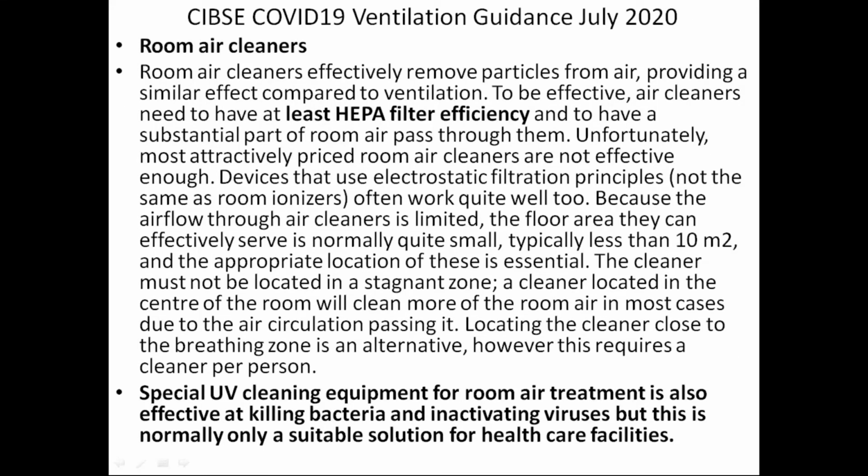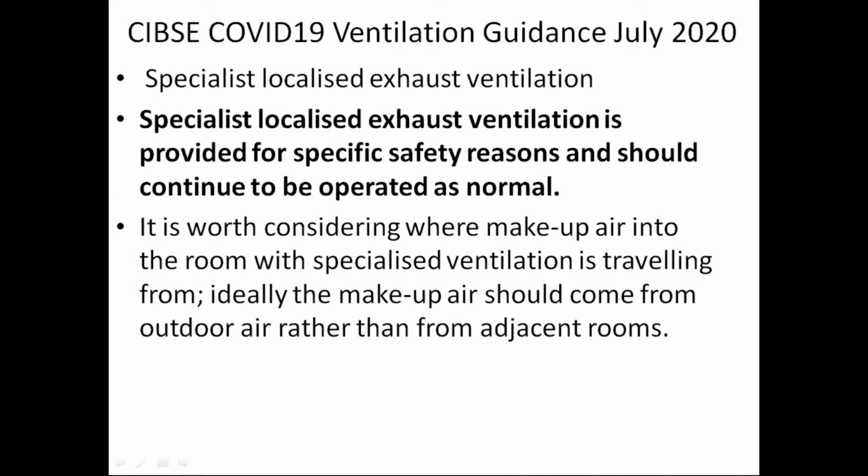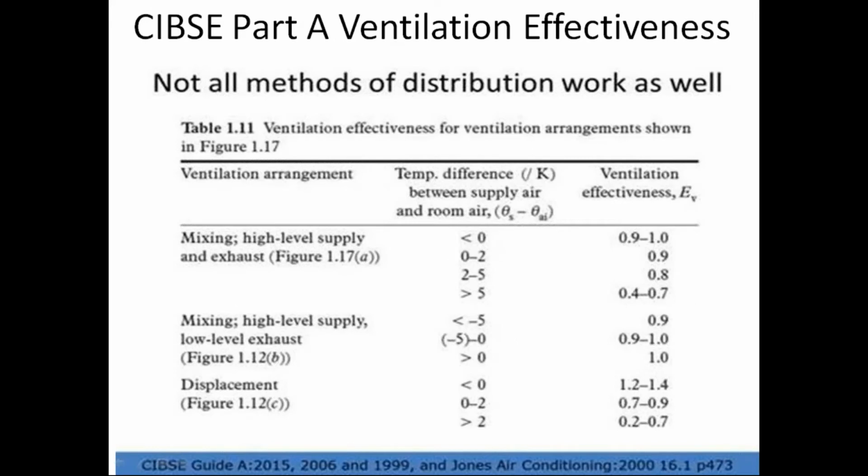Room air cleaners are acknowledged within CIBSE, but they have to be HEPAs, and they have to be to the standard that Camfil explained on previous ASHRAE presentations. They do acknowledge UVC as well. Local exhaust is important, particularly where you have AGPs, and catching the source locally and dumping it in a safe location is important. Ventilation effectiveness is important because you need to know that you have good dilution and good mixing in the room. CIBSE give guidance on this.